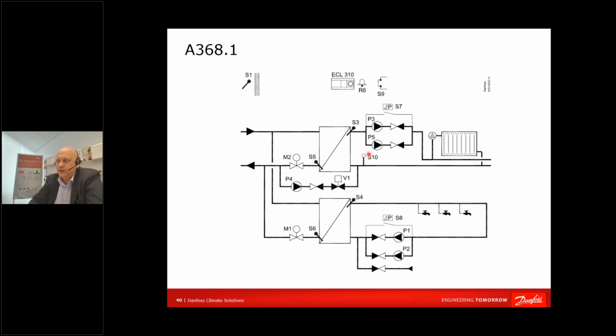Some applications like ECL A376 have a possibility of an externally operated relay. So when you are connecting to ECL Portal, you can actually have more pressure sensors connected. You can monitor them, and if you discover that some of the circuits is missing water, you can externally, via internet, switch on, switch off. That's complicated. I would say that it's not a ready solution for an easy set and go. So with a pressure sensor, two circuits can be controlled. Yes, easy. If you need three circuits, then probably I would advise two ECLs to control it. Yep.